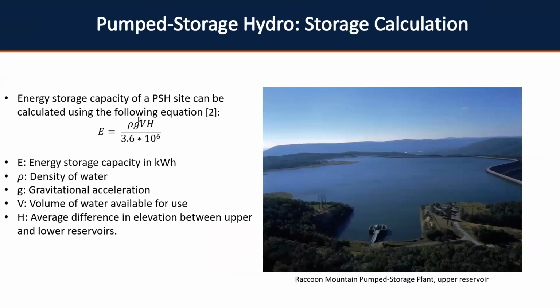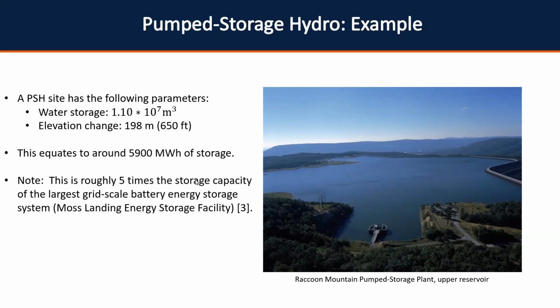Here is, pretty much straight out of the book, the energy storage equation. I did change it a little bit just to make it easier to read. Energy storage in kilowatt hours equals density of water, times gravitational acceleration, times the volume of water available for use. That's not how much is in the upper reservoir. That's how much you can drain it down, so there's a little bit of a difference there. And then times the average difference in elevation between the upper and lower reservoirs.